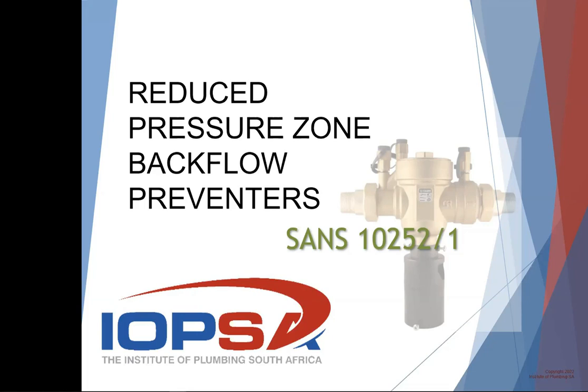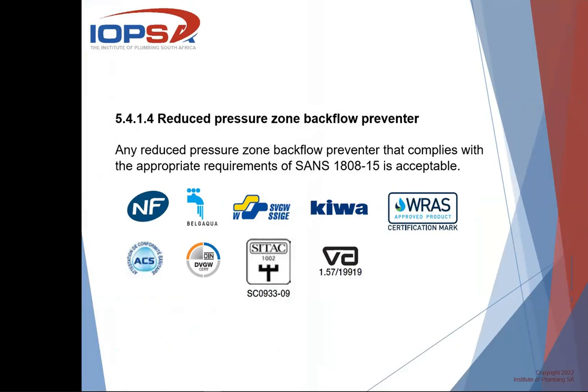When you are doing a new installation, it is law that you have to include an RPZ valve. But do all installations need an RPZ valve? We're going to have a look at SANS 10252 Part 1, which covers water supply to houses and any installation, and specifically clause 5.4.1.4, where it says any reduced pressure zone backflow preventer that complies with the appropriate requirements of SANS 1808 Part 15 is acceptable.